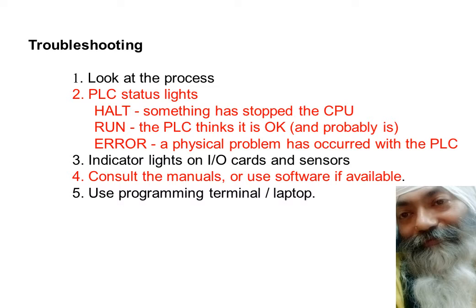You can force the output off to check whether the actuator is coming back to zero. Similarly, you can force some of the input bits on to check whether the program is working as per your desired value or not.